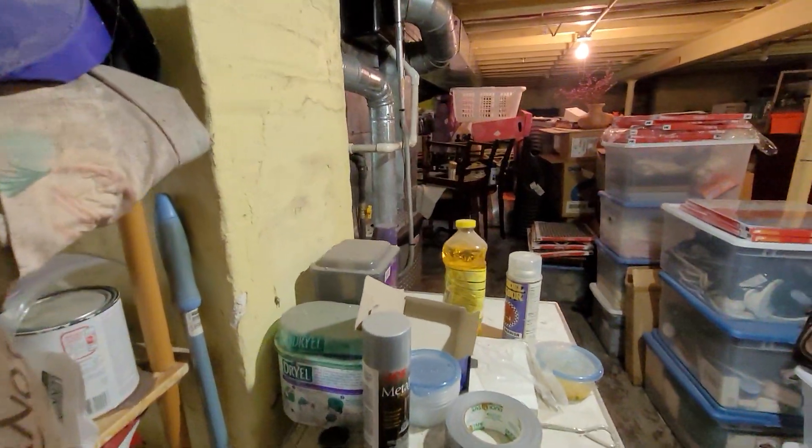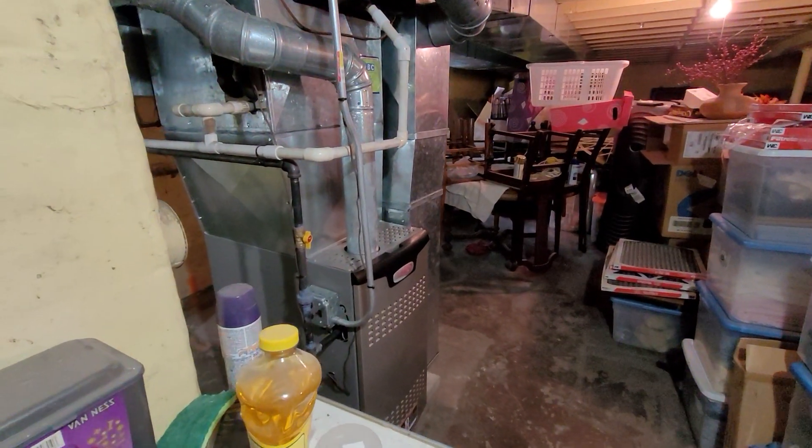So a condensation pump is going to have to go in. We're looking at most likely a two-and-a-half ton air conditioner, 17 inches wide. The electrical is basically new — that is a Siemens box with a 30 amp breaker in it.